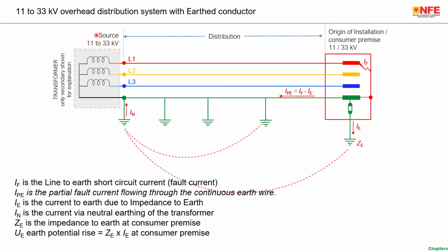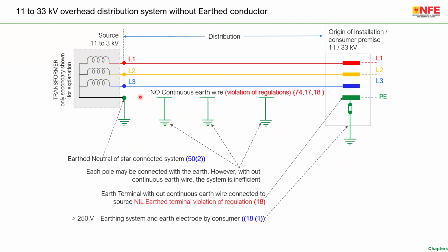Now, if we look at the standards, any Indian standard, 60909 or any of the international standards, there is no system explained without this IPE. That means without a metallic fault return path, there is no system explained. Why I made this statement is, in India, if we look at some of the states, I won't say all the states, some of the states, if we look at the 11 kV distribution on the roadside, you will see only 3 lines, RYB. The fourth wire is totally missing. There is no continuous earth wire, which is a violation of regulation 74, regulation 17 and regulation 18. So basically, no continuous earth wire in an overhead line is a violation of the regulation.